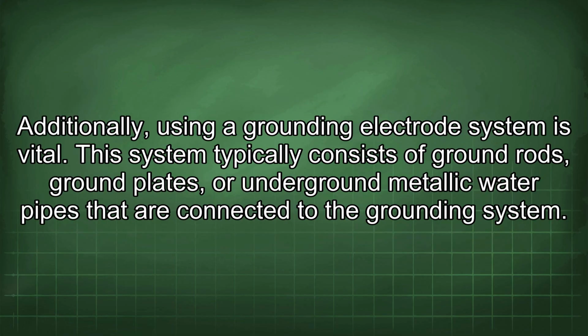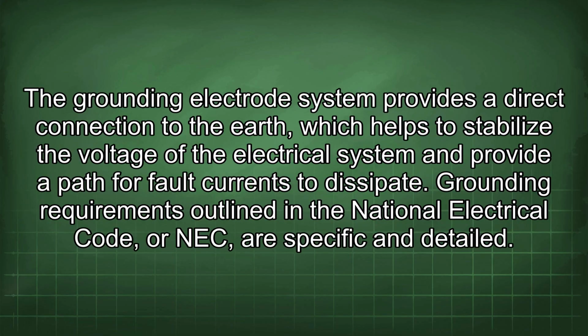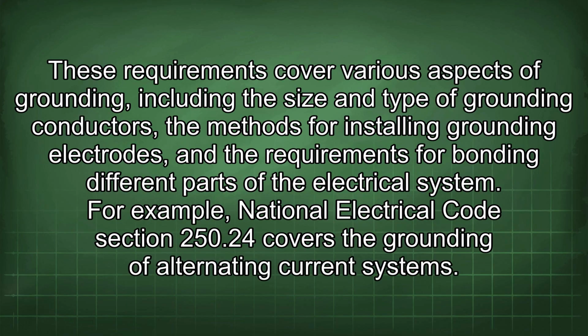Additionally, using a grounding electrode system is vital. This system typically consists of ground rods, ground plates, or underground metallic water pipes that are connected to the grounding system. The grounding electrode system provides a direct connection to the earth, which helps to stabilize the voltage of the electrical system and provide a path for fault currents to dissipate. Grounding requirements outlined in the National Electrical Code, or NEC, are specific and detailed. These requirements cover various aspects of grounding, including the size and type of grounding conductors, the methods for installing grounding electrodes, and the requirements for bonding different parts of the electrical system.